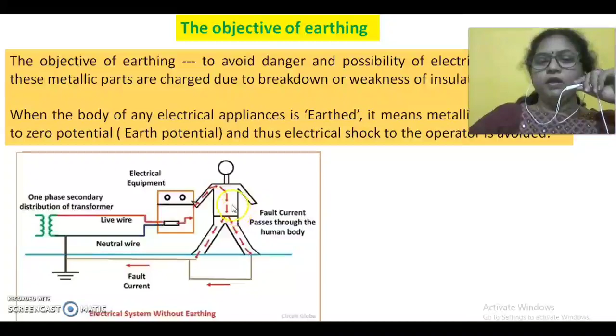But if the system is not connected to earth, without earthing, the metal frame is not grounded — either a 2-pin plug is used or the surface is not grounded. Now in this case, if a live terminal touches this metal, the fault current will flow through the person in contact with this equipment, and it is dangerous for this human if the fault current is more than 150 milliampere.